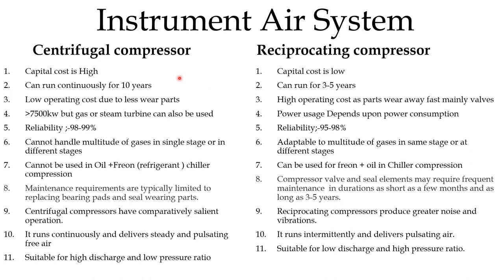Now we can see the comparison between centrifugal compressor and reciprocating compressor. Centrifugal compressor capital cost is very high compared to reciprocating compressor, which has a low capital cost. Centrifugal compressor can continuously run for 10 years, whereas reciprocating compressor can run for only 3 to 5 years. For centrifugal compressor, operating cost is low due to less wear of parts. For reciprocating compressor, high operating cost as parts wear away fast. Centrifugal compressor power consumption is greater than 7500 kW, but gas or steam turbine can also be used.